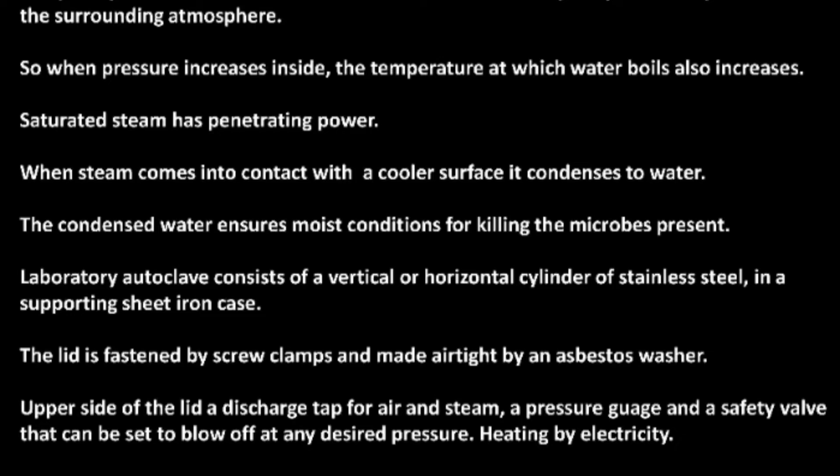A laboratory autoclave consists of a vertical or horizontal cylinder of stainless steel in a supporting sheet iron case. The lid is fastened by screw clamps and made airtight by an asbestos washer. On the upper side of the lid there is a discharge tap for air and steam, a pressure gauge, and a safety valve that can be set to blow off at any desired pressure. Heating is by electricity.